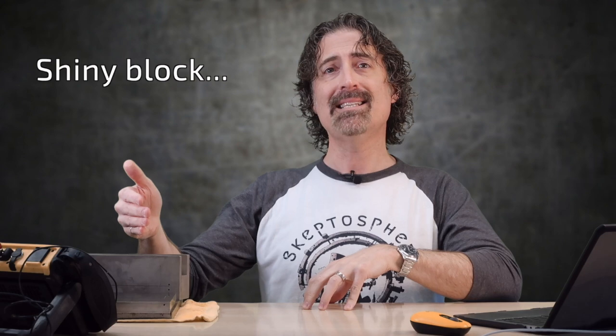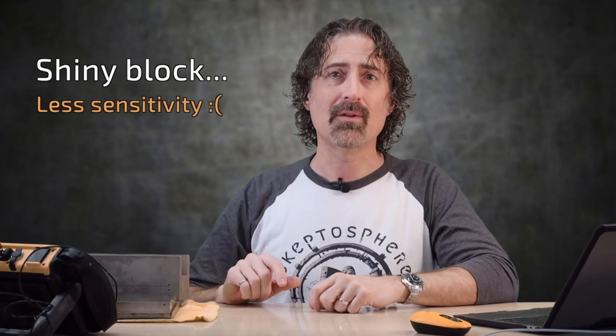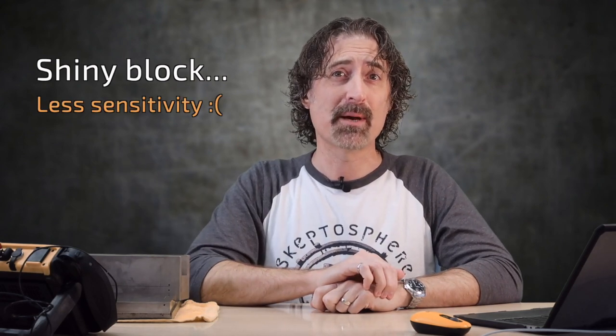If you use a nice shiny calibration block to do the TCG, the reference signals in there are going to be really loud because the surface is so nice. So what happens is you end up making a TCG with a lower reference level, and that means a less sensitive inspection. Let's take a look at a practical example.